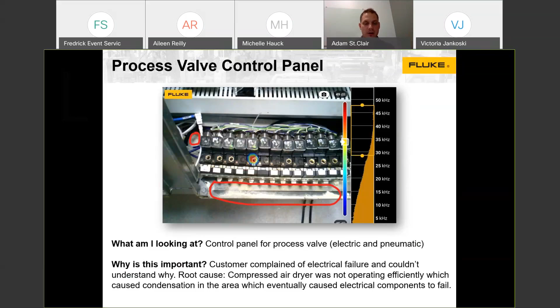What we found was that one of the compressed air dryers wasn't operating efficiently to pull condensation out of this control panel, resulting in condensation and moisture buildup. When that moisture reached a certain level, it caused the electrical components to short out. A neat example, because we thought the root cause was electrical, but it turned out to be mechanical, and the ii900 helped us quickly get to the root cause, completely different from what any of the folks on this team thought it was.